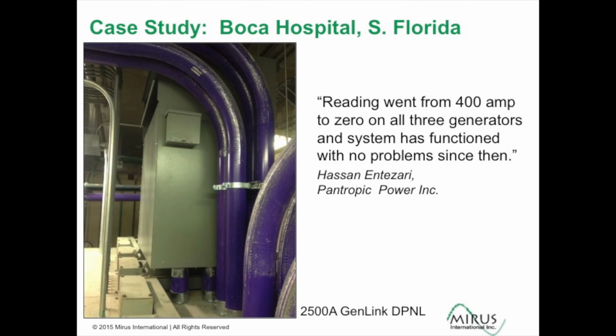We didn't get a chance to go back and take measurements, but the engineer that did the installation did say that prior to the installation of the DPNL, the circulating current was actually in the range of 400 amps, so much higher than the predicted 200 amps from the calculations. But after the DPNL was installed, they could not measure any circulating currents, so we virtually eliminated it altogether, and all of their problems had disappeared.